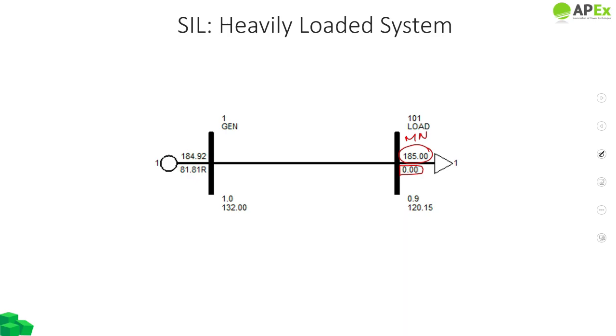However, due to the characteristics of this line being loaded above its surge impedance loading, which we found as 48.84, this line is consuming megawatts. Because of this consumption of megawatts by the transmission line, there is a drop in voltage at the receiving end. The receiving end voltage is down to 0.9 per unit or 120, while the sending end unit shows that the generator here is producing 81.81 megavars.